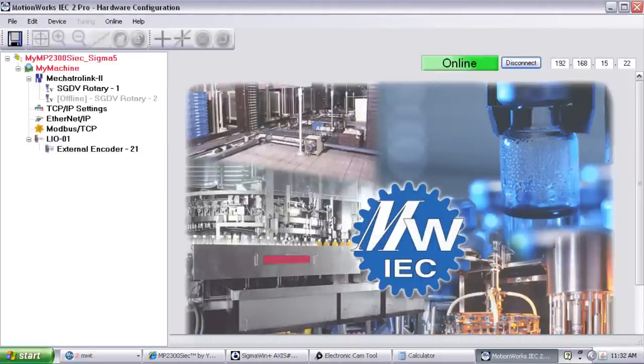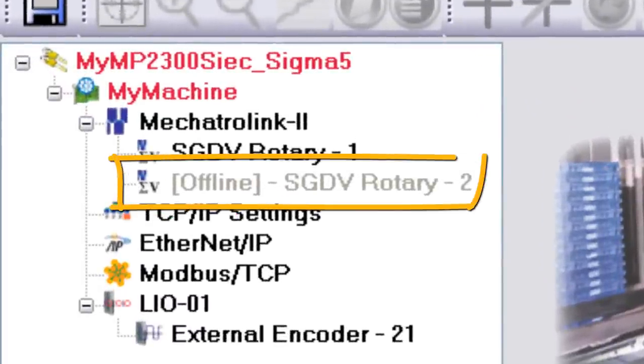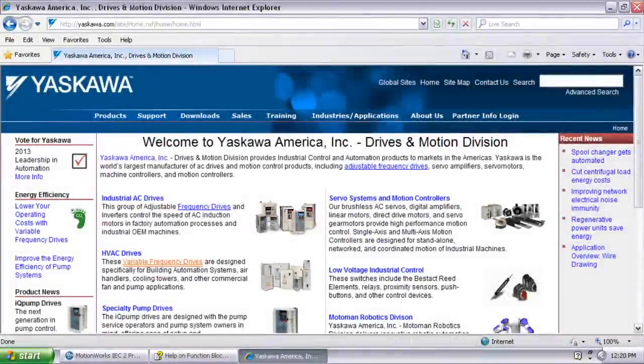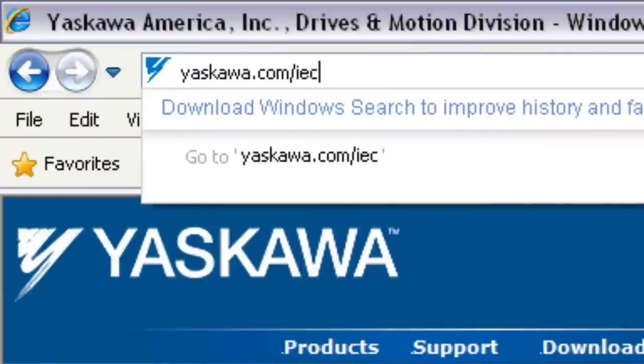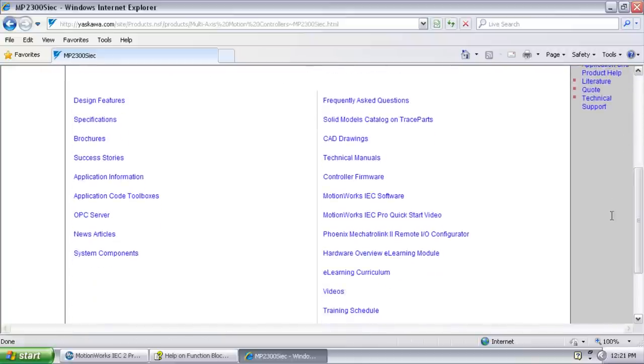MotionWorks IEC hardware configuration will indicate the problem with 'offline' in the grayed-out axis name. If two devices are set with the same node address, neither will operate. Thanks for watching this video, and remember yaskawa.com/IEC for application notes, videos, and more.